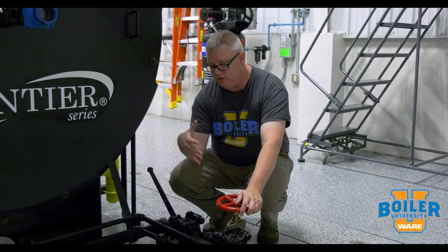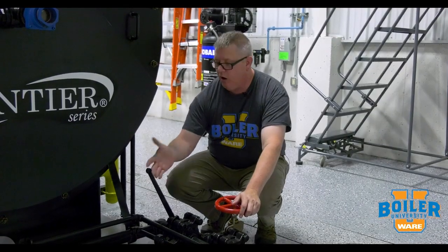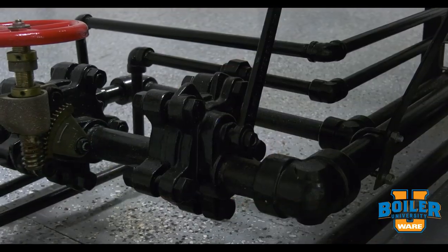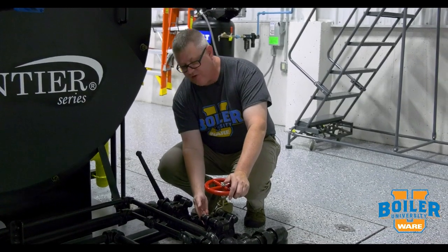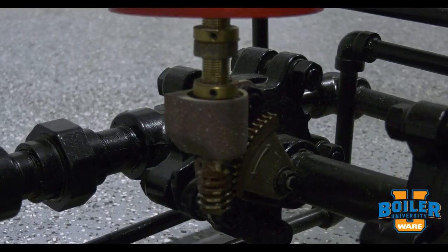What's interesting is that the valve bodies are actually identical. The only thing that's different between these bodies is the opening mechanism. On this one we've got a lever connected directly to the valve shaft. On this one we have the same valve shaft, simply being driven by a screw, with our slow opening valve.